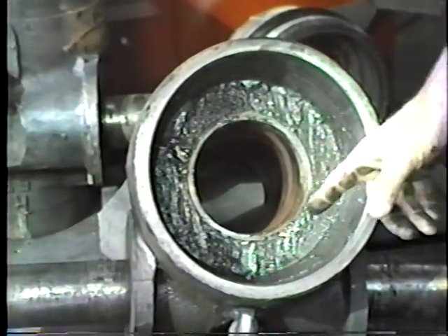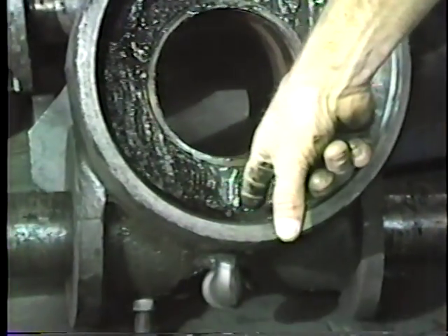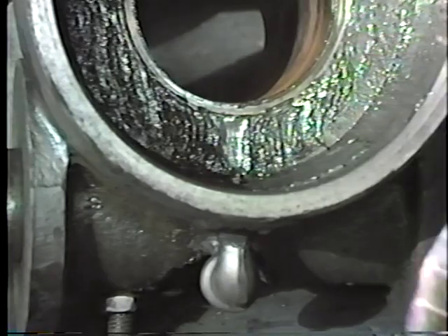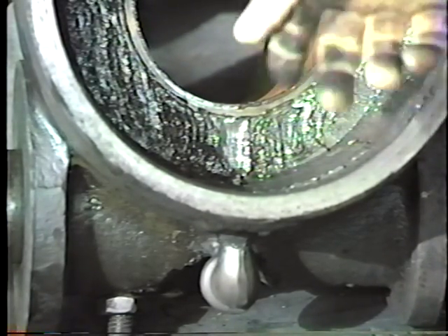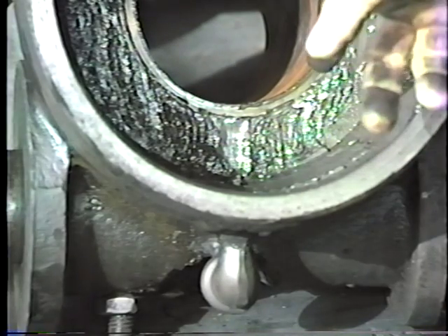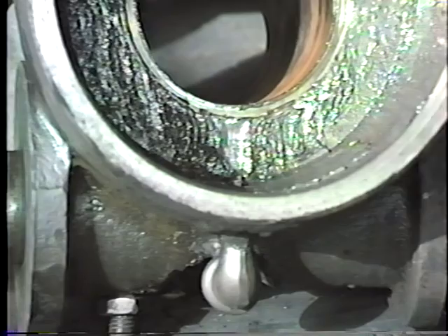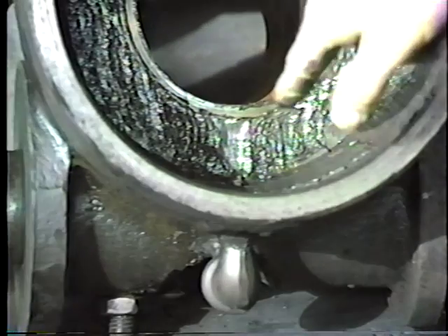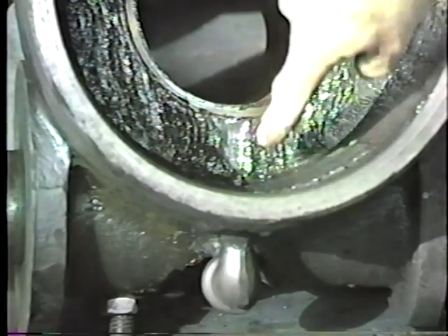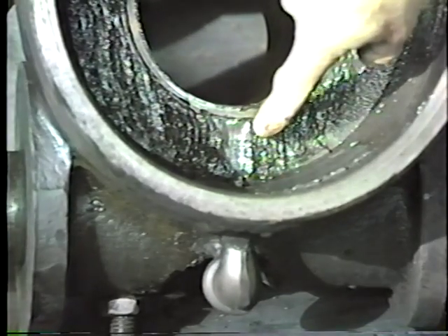Will you point to the air seal? Is it plugged? No, it's not plugged. How can you tell? Well, when I took the air seal off, it wasn't even plugged. It was clean. You can see where the air was coming in, so that's a sign that the air was actually going in there at that location.